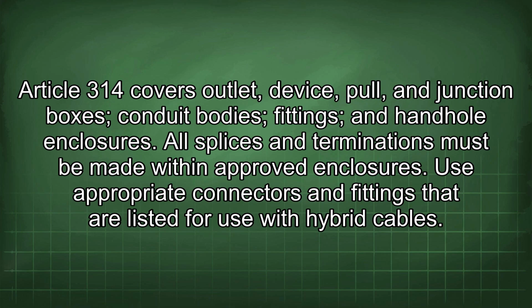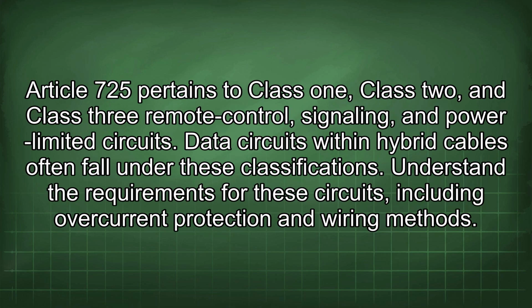Article 314 covers outlet, device, pull, and junction boxes, conduit bodies, fittings, and handhole enclosures. All splices and terminations must be made within approved enclosures. Use appropriate connectors and fittings that are listed for use with hybrid cables. Article 725 pertains to Class 1, Class 2, and Class 3 remote control, signaling, and power-limited circuits. Data circuits within hybrid cables often fall under these classifications. Understand the requirements for these circuits, including overcurrent protection and wiring methods.